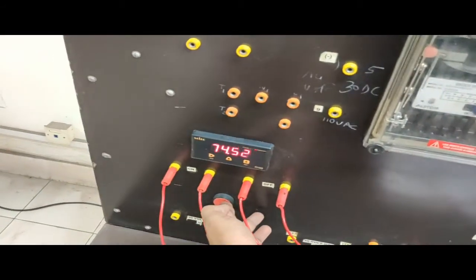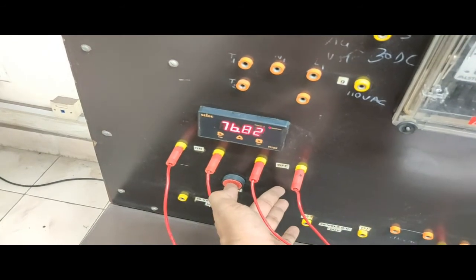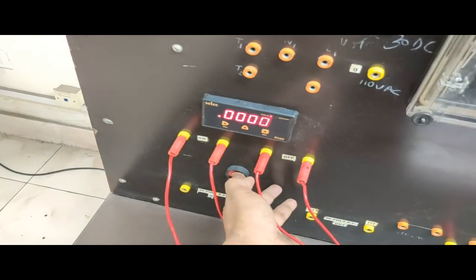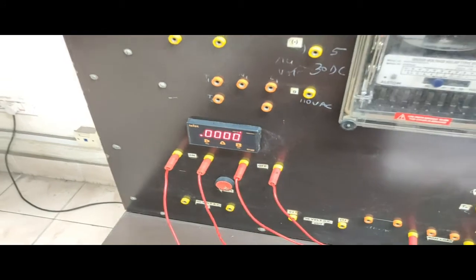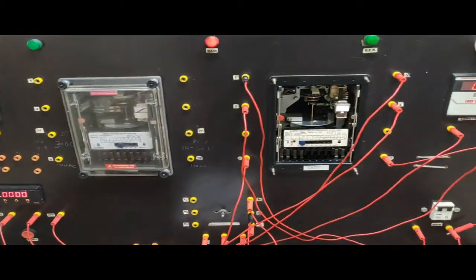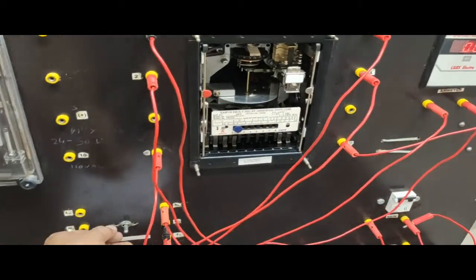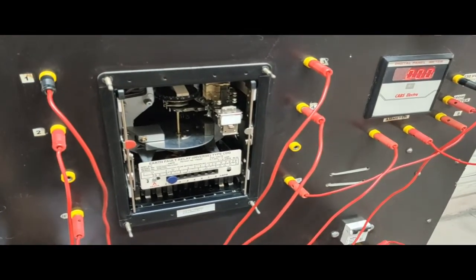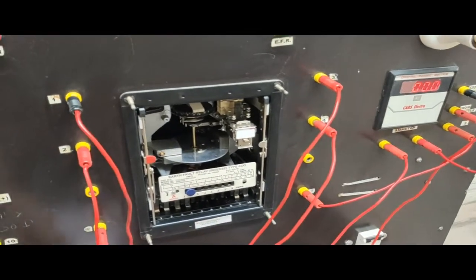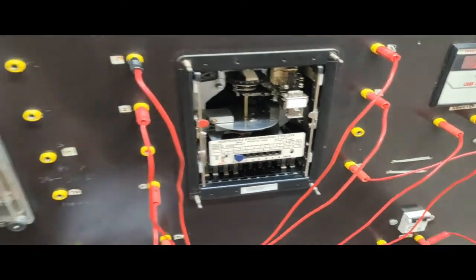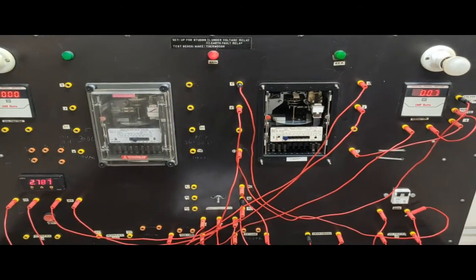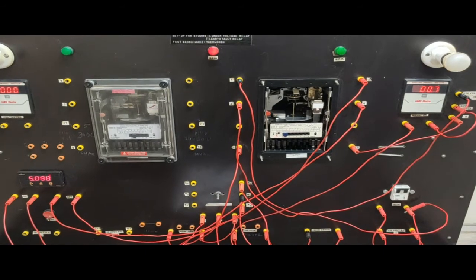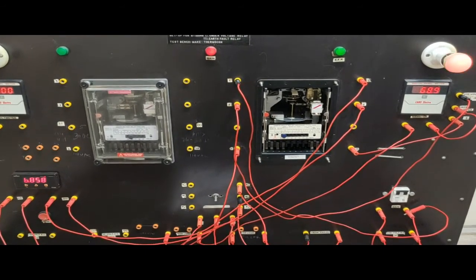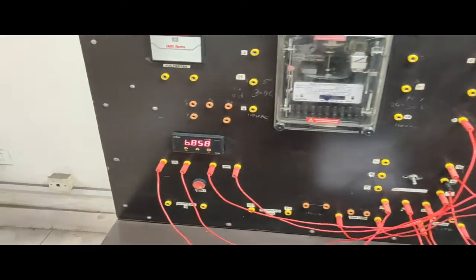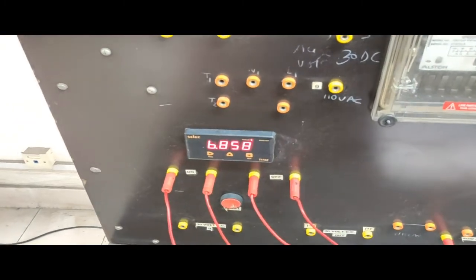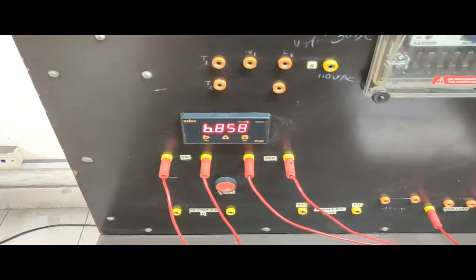So for that I need to reset the timer again. To reset the timer, just press and hold this reset switch for a while to make the timer reset. Now I apply the required amount of voltage so that 0.6 ampere current will flow to the relay coil. So just press it and you see the relay is moving, the timer is counting, and here you see that 6.858 seconds is required to operate the relay.